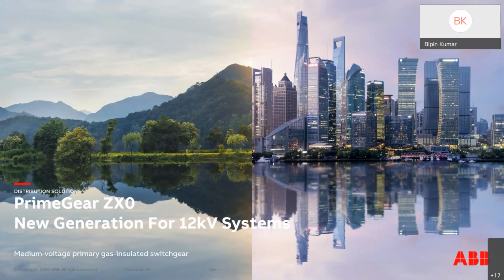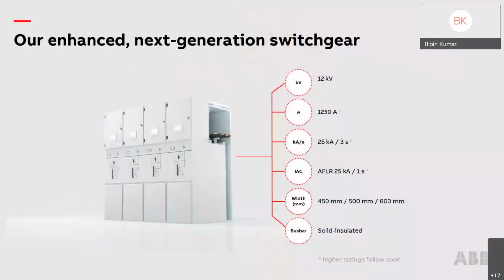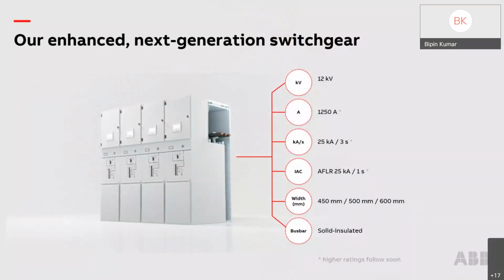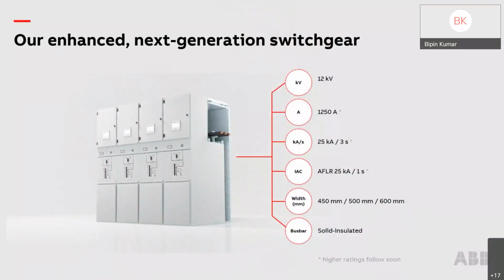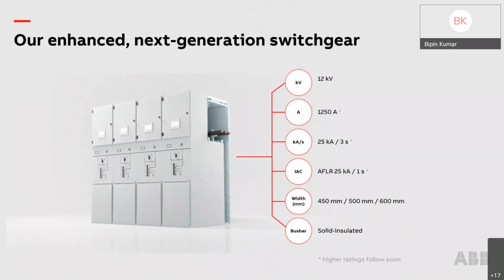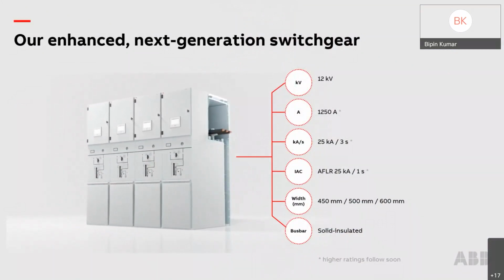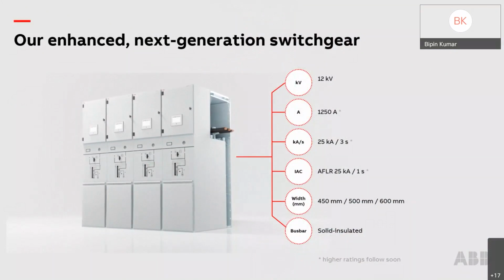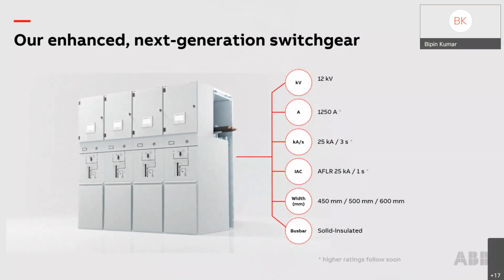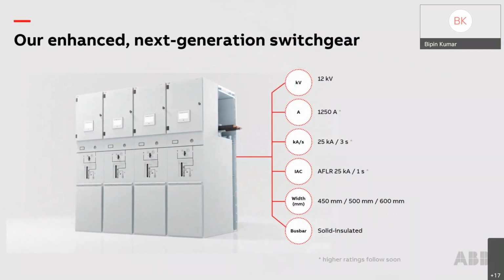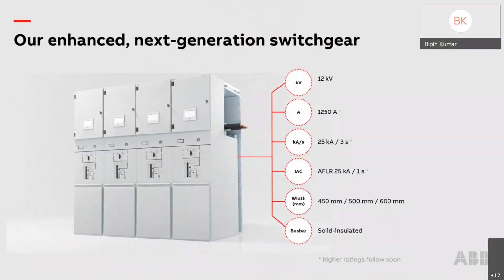What I'm presenting to you is a new generation 12 kV gas insulated switchgear. As spoken at the start itself, we can all see that from the switchgear industry side we are trying to move from an air insulated switchgear towards a gas insulated switchgear. Of course, it is much more predominant on the 33 kV side, but there are many things happening, and many of the utilities are also coming up with the requirement of 11 kV systems.